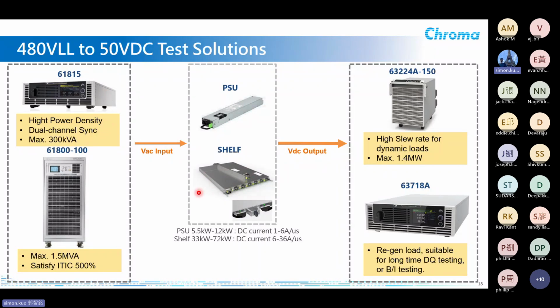And another good part is that the shelves are running with 2 AC inlets because of the current limitation. One of the customers proposed that they want to do different voltages. They want to do 110 volts 60 hertz on one AC input, and 230 volts 50 hertz on the other AC input, but they want to run the same sequence of power line disturbance tests, such as AC dip or AC pulse. In this case, we will suggest the customer use the 61815. So you have two groups of the 61815 to run the dual channel synchronization test. But anyhow, if you face this kind of requirement, you can reach out to us. We have the slides ready for that.